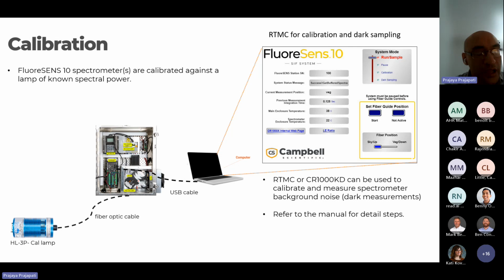Another important step is the calibration. Calibration is required to convert the pixel count we measured from the spectrometer to the unit of irradiance, and this is done by feeding lamp light to the spectrometer. This lamp light has known intensity for known wavelengths, and all the customer needs to do is use this graphical user interface that's based on RTMC, pause the system and bring the system mode to calibration, and the data is saved in the raw data file, which can be used later in post-processing for calculating a conversion factor.